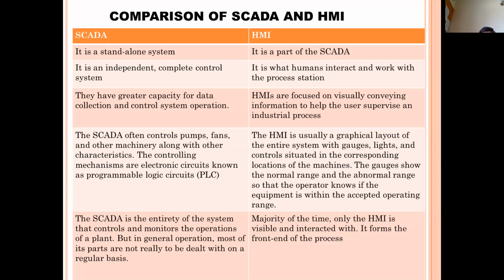A human needs to interact with the HMI. That is the word itself, HMI, human machine interface. In the HMI we have a small window. It has a touch panel, so it's a graphical layout. Whatever mimics are created in the SCADA and the HMI are one and the same. The only thing is the HMI is used for a part of the plant, whereas the SCADA will have the mimic screen for the whole plant.